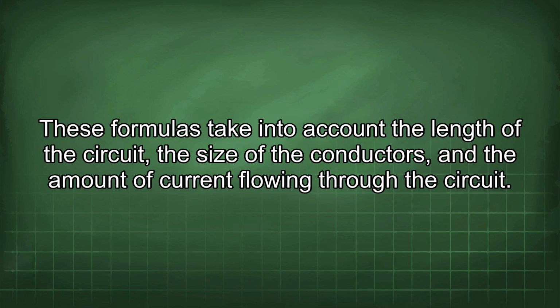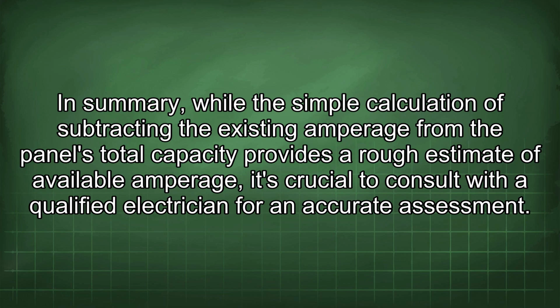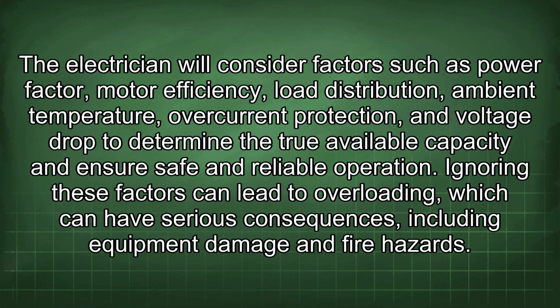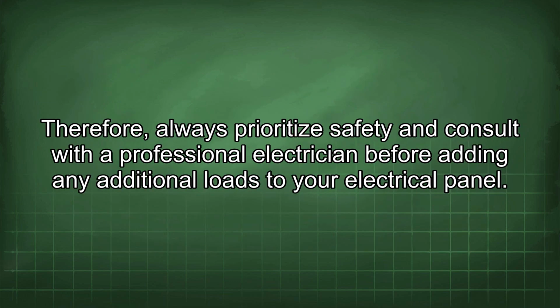In summary, while the simple calculation of subtracting the existing amperage from the panel's total capacity provides a rough estimate of available amperage, it's crucial to consult with a qualified electrician for an accurate assessment. The electrician will consider factors such as power factor, motor efficiency, load distribution, ambient temperature, overcurrent protection, and voltage drop to determine the true available capacity and ensure safe and reliable operation. Ignoring these factors can lead to overloading, which can have serious consequences, including equipment damage and fire hazards. Therefore, always prioritize safety and consult with a professional electrician before adding any additional loads to your electrical panel.